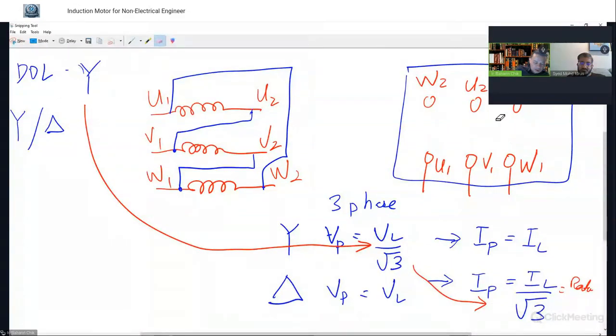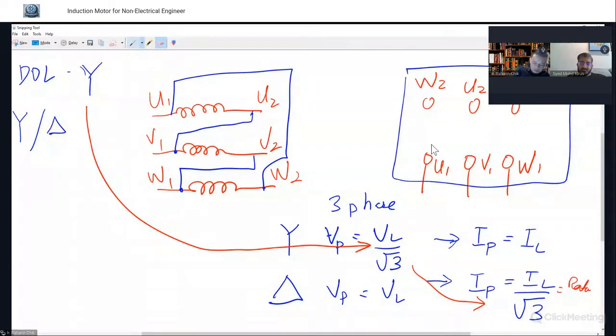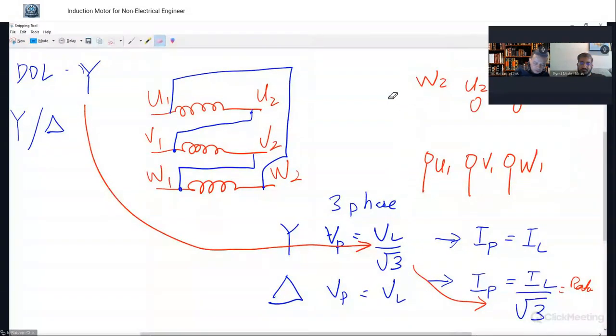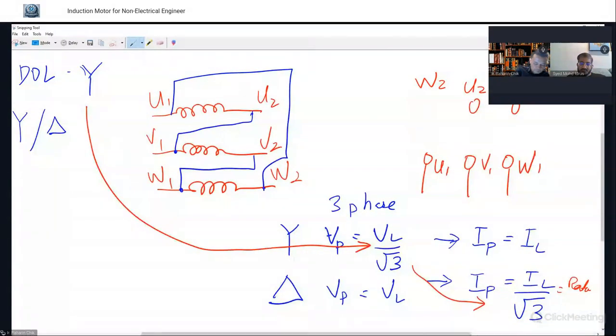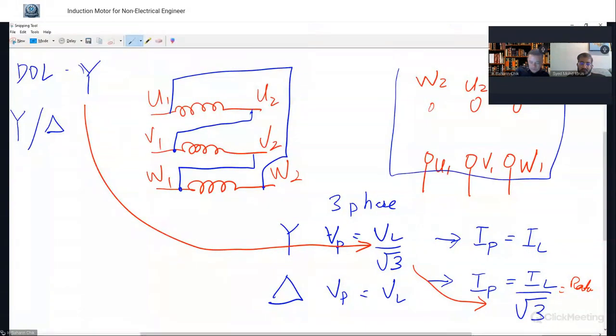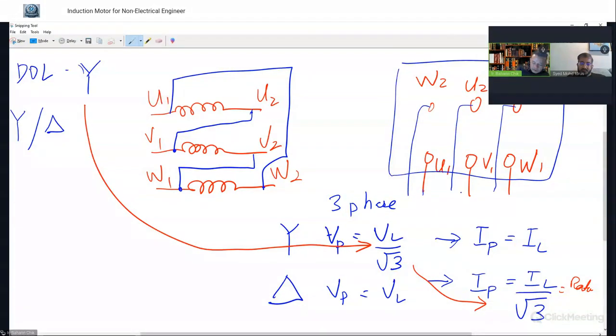Now, when you have star delta, you have to bring all this connection out. So instead of supplying the voltage here, you're going to take this out to the controller in the switch gear. So now instead of having 3 core cables, you have to have six core cables, and then this will go inside your MCC.